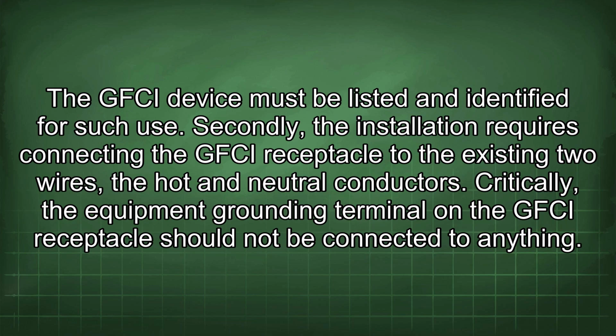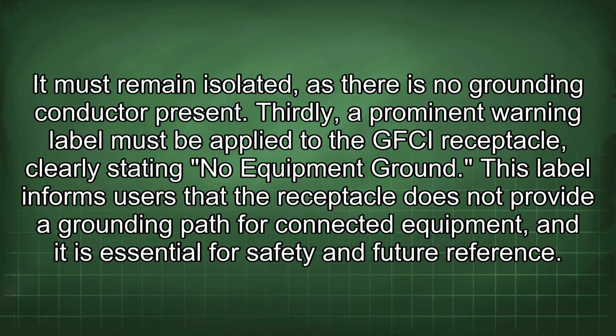Secondly, the installation requires connecting the GFCI receptacle to the existing two wires, the hot and neutral conductors. Critically, the equipment grounding terminal on the GFCI receptacle should not be connected to anything. It must remain isolated, as there is no grounding conductor present.